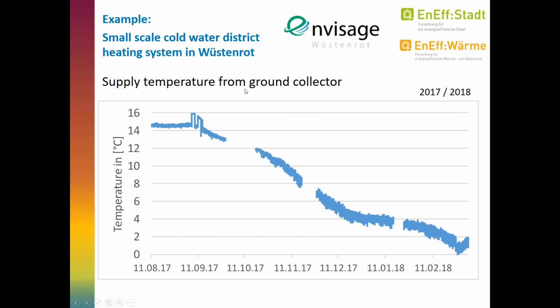Here you see some operational measurements of the supply temperature which comes from the cold district heating network. As you can see, it's not constant, because we are using the ground at 2 meter depth, and it depends on the seasonal conditions what temperature you can extract from the ground. So it varies between roughly 15 and 1 degree supply temperature, depending on the outside temperature and how deep this goes.